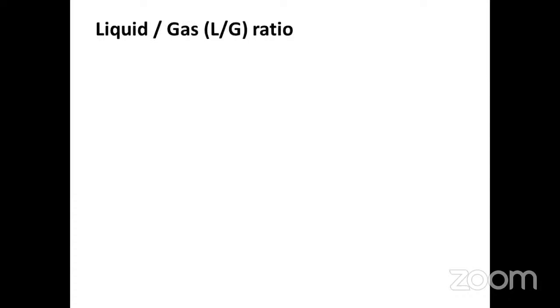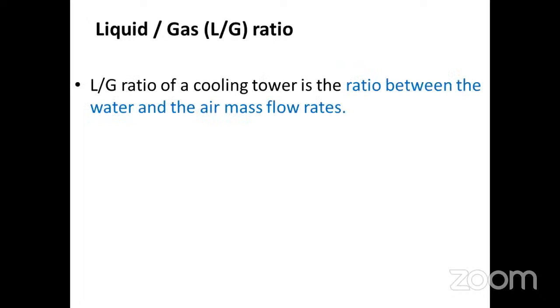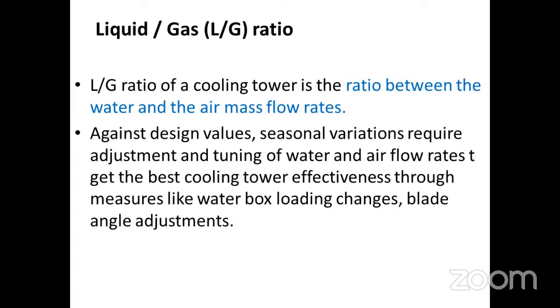One more term, liquid bar gas ratio. The L bar G ratio of a cooling tower is the ratio between the water and air mass flow rates. They are calculating it in an indirect way. Circulating water can be directly inferred from the flow of the motors, but for this one, they have a different formula. Against design values, seasonal variations require tuning of water and air flow rates to get the best cooling tower effectiveness, through measures like water box loading changes and blade angle.